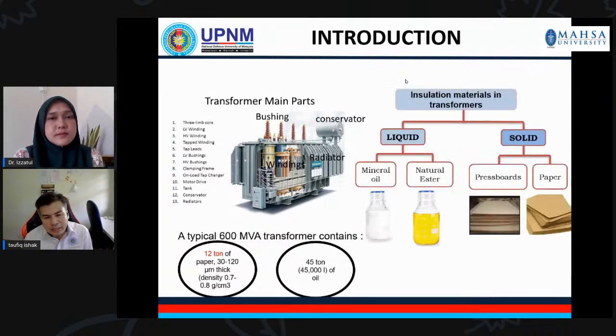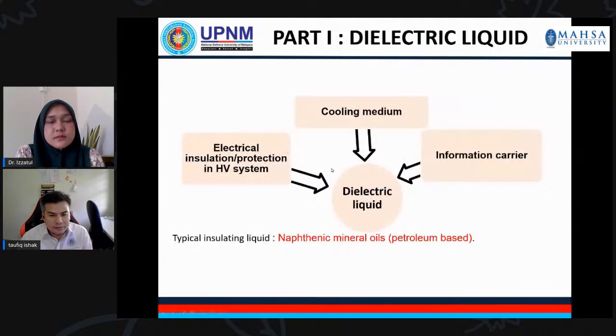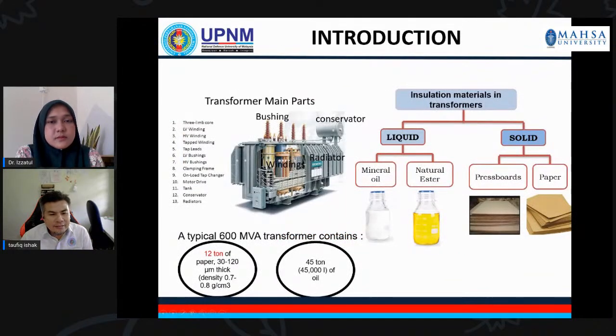Inside the transformer tank, we normally have transformer oil. Its function is to cool the transformer as well as to give insulation between the electrical part and the ground, the grounding of the transformer. For example, a typical 600 MVA transformer normally contains 12 tons of paper, with a thickness between 30 to 100 micrometers and a density between 0.7 and 0.8 gram per cubic centimeter. Inside that transformer, we can have 45 tons, or 45,000 liters, of oil.